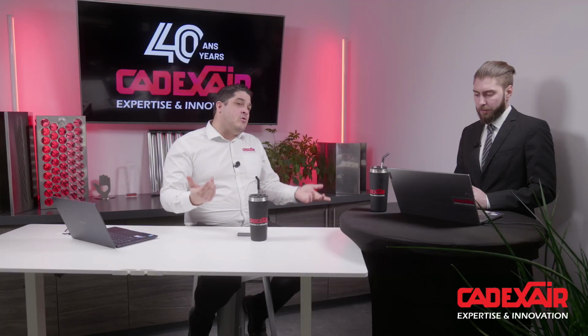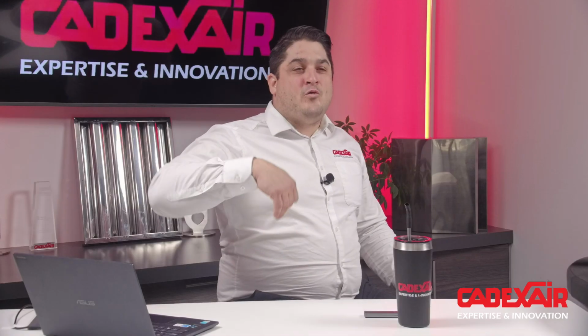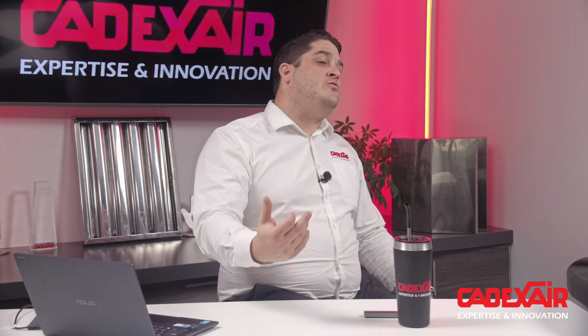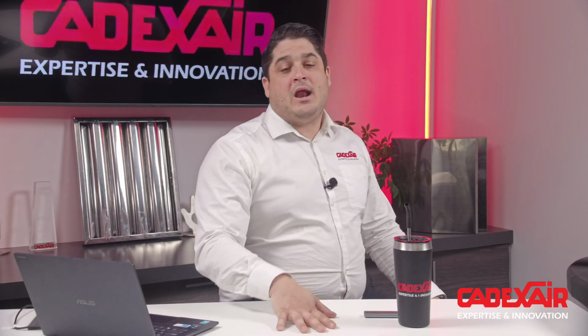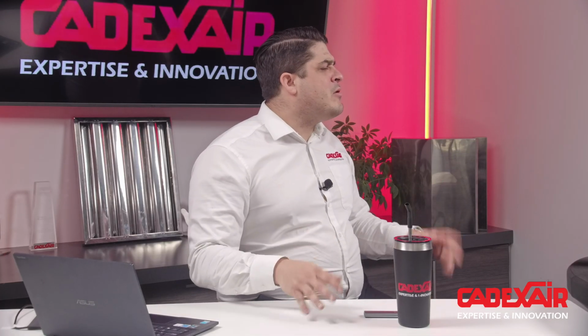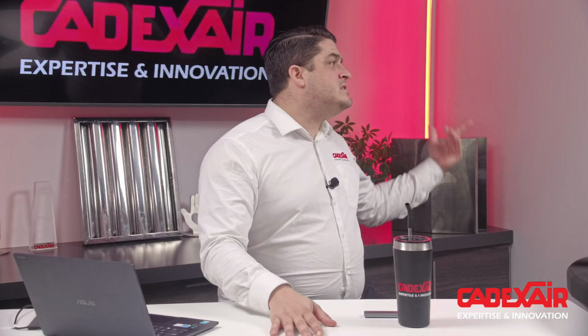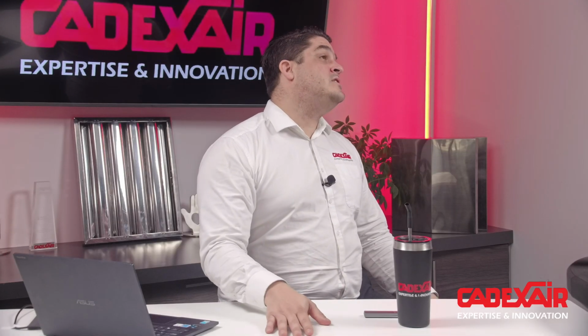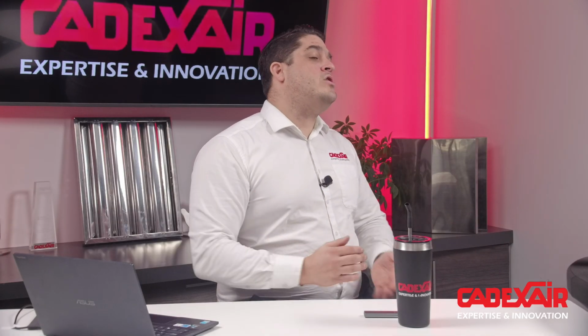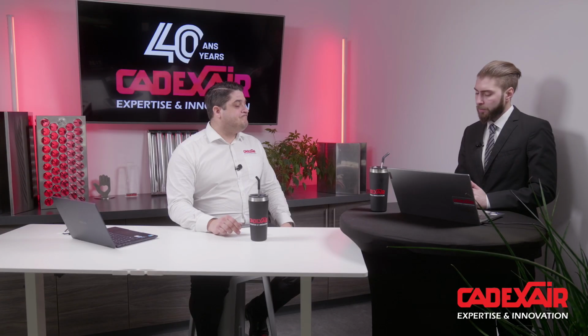If we lose power, we shut it down because we don't know if it will come back in 2 or 5 hours. So we have to reset the system. In that case, if we have a UPS, it will allow the system to operate probably for around 15 minutes with the lights in the hoods and also the gas valve. So if you have that kind of setup, it will be a little bit steadier.